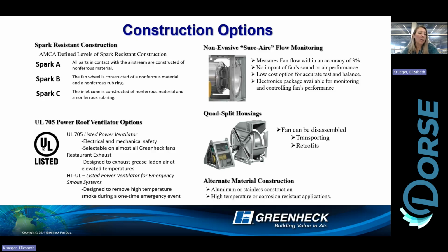Some of the fans needed to be upgraded in order to move more CFM, and that was actually pretty easily done with that belt drive configuration. So that's, I guess, a benefit of a USF that's belt drive. You can upgrade the motor, you can upgrade the drives to provide the air that's needed. With the emergency smoke, with the UL smoke, that is always tested in the building. So if it is ever short on air, I would say choose a belt drive for those emergency smoke applications.